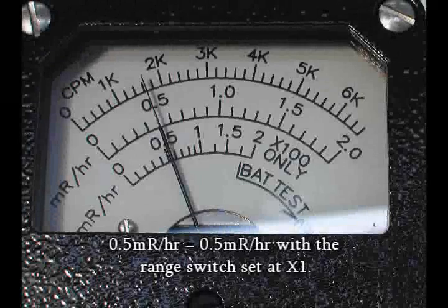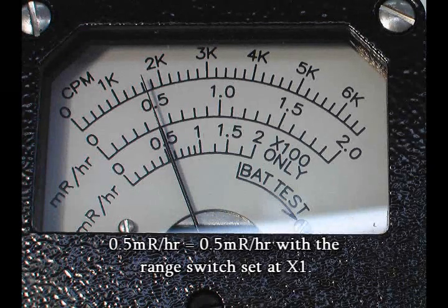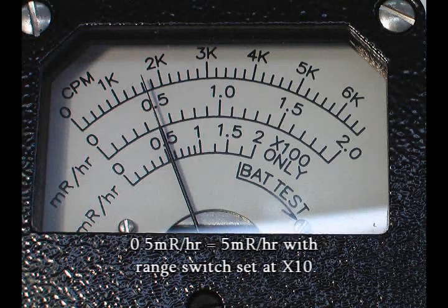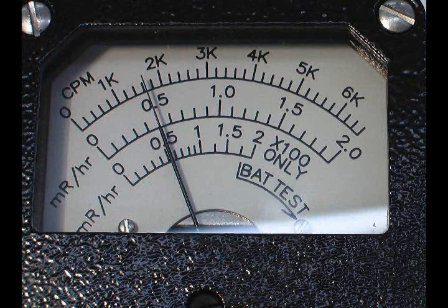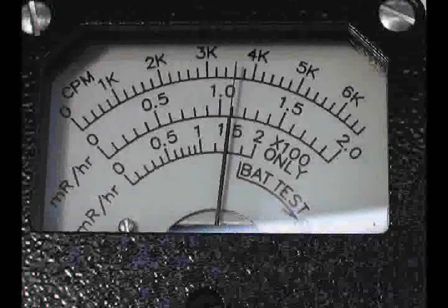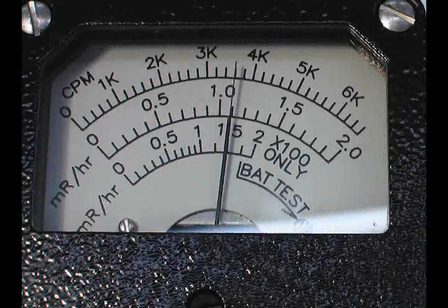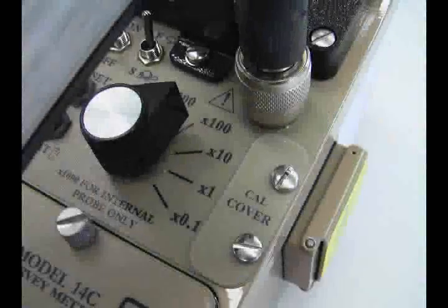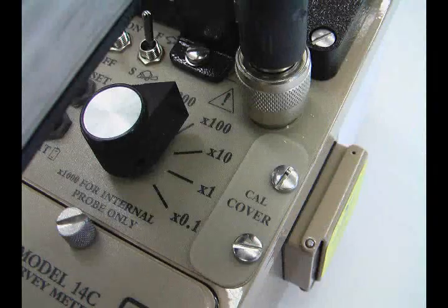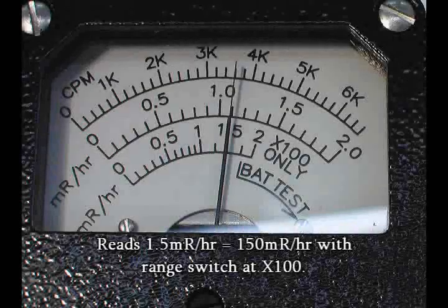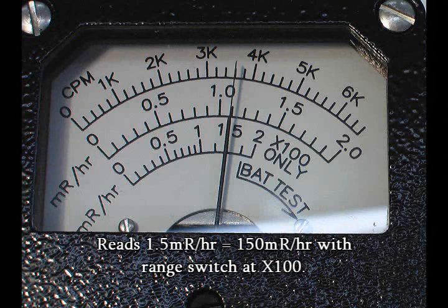Moving to the times 1 position changes the reading to 0.5 millirem per hour. Moving to the times 10 position changes the reading to 5 millirem per hour. The middle scale is only valid with these 3 settings. In this example, reading the bottom nonlinear millirem per hour scale with the range selector switch in the times 100 position, the meter needle is on the 1.5 tick mark. This will be read as 150 millirem per hour.